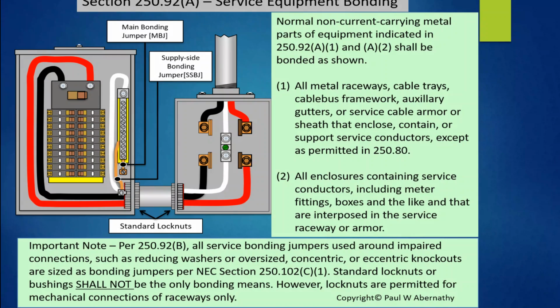So that means you're going to have a bonding bushing with a bonding jumper on it. If these were perfectly knocked out openings, meaning there are no rings left in it, or you punched them yourself, like in larger equipment where you have a hole punch, a Greenlee for example, they make one, then you use the raceway on it, and you could use what's called a bonding lock nut. You can never use a standard lock nut for any of this special service type of bonding. You can use it for mechanical purposes to hold it all together, but you can't use it to make that real important assured type of bonding connection.